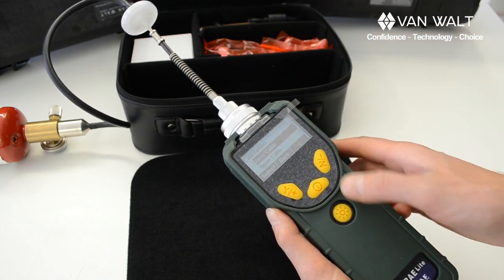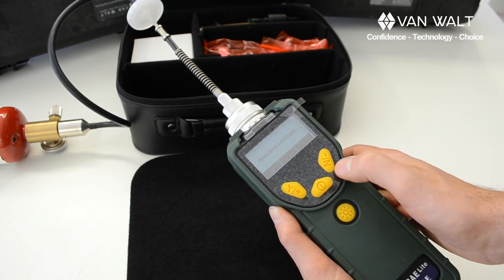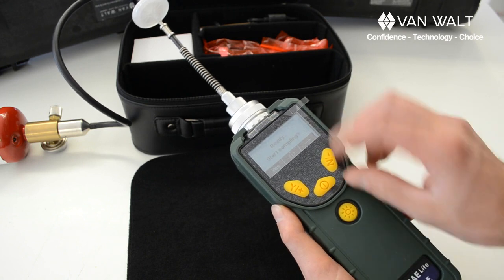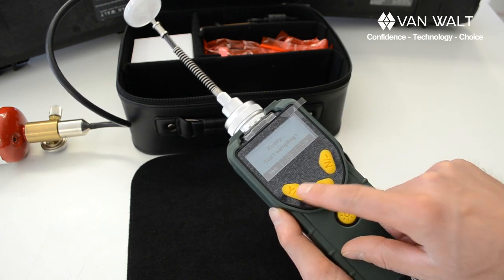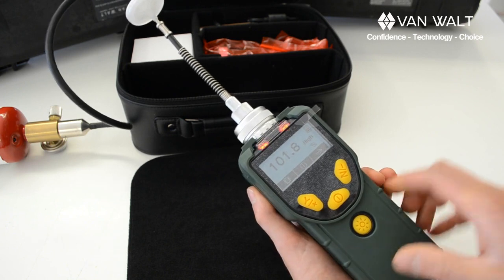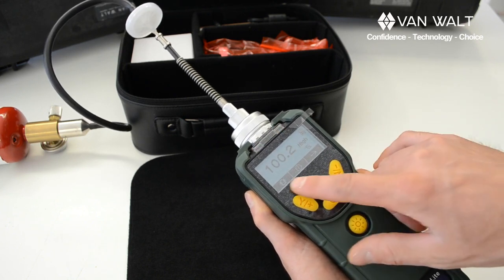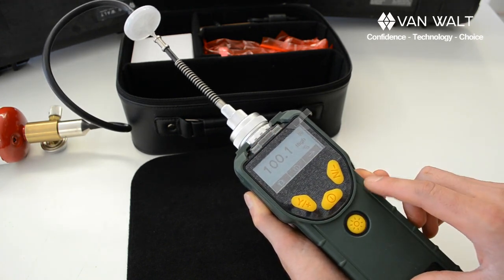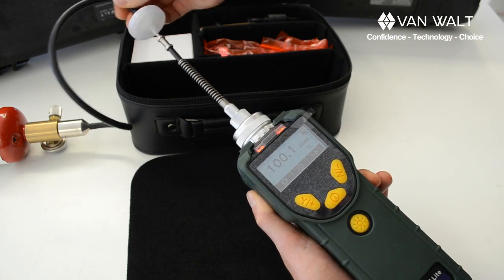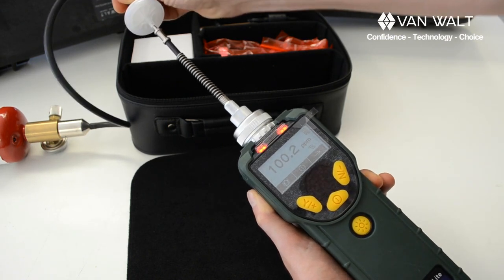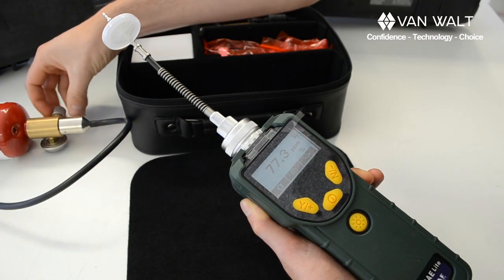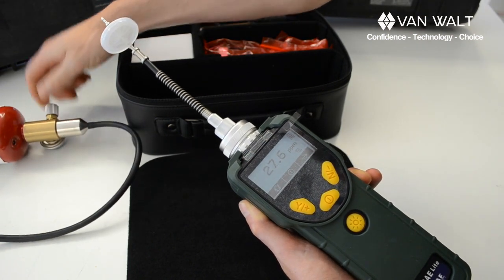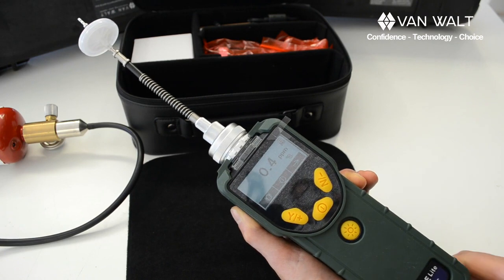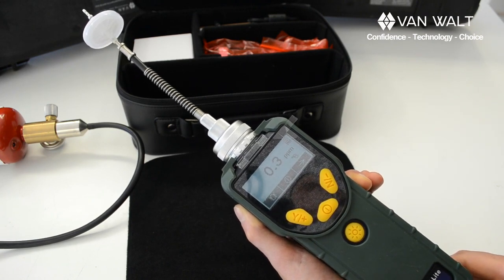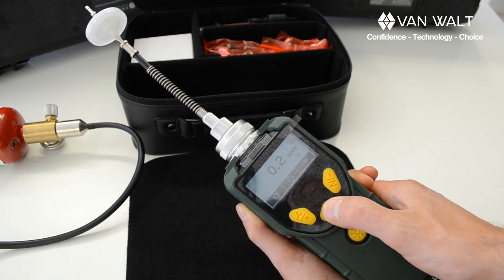So before I disconnect the gas, I'm going to press the back button. It's updating its settings. Go back to start sampling, yes. And this is again a bump test, and again near as makes no difference, 100 ppm, so it's pretty good. Take the gas off. And that should recover fairly quickly to near as makes no difference, 0 parts per million in the fresh air. And to turn the machine off, just press and hold the power button.